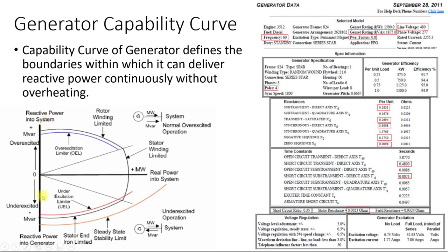Here is a typical reactive capability curve. What this curve tells us is that for a certain amount of active power, what is the reactive power that can be provided by the generator. This point represents Qmax and this point represents Qmin. If the generator is operating at a given active power level, we can read off the corresponding Qmax and Qmin values, and we must ensure that when providing active and reactive power to the generator, we do not exceed its limits.